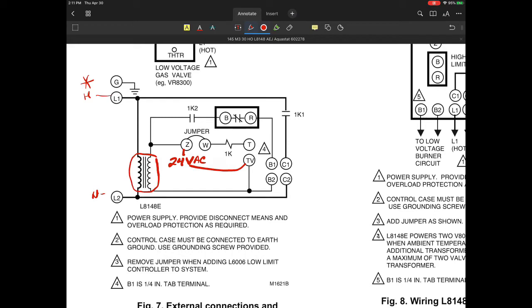So that's one advantage. I can actually get between terminal Z and terminal TV, and I can verify that transformer by measuring 24 volts whether there's a heating demand or not. I can always get 24 volts on there, assuming that I've got my 120 volts hot and my neutral, obviously, to this device. So all the time that is.